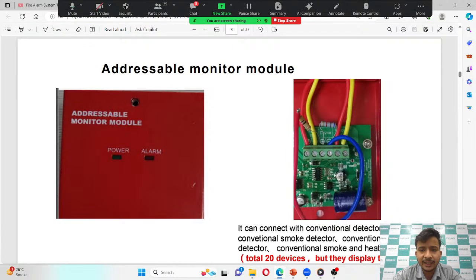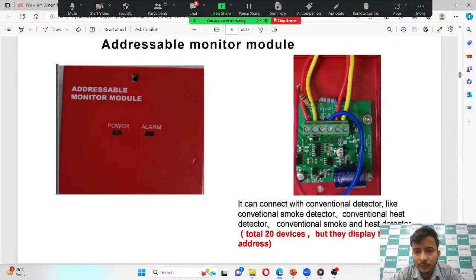Then this is the wiring scheme for the addressable monitor module. As you can see, we have 3 Phoenix connector ports. One is for loop in, as it will be added in a loop, and another one is for loop out. The third one is for adding the device, whatever you are adding, either a conventional smoke detector or heat detector. So one port is for adding that device, and this port has one resistor also. This resistor is mandatory for the communication. If this resistor is removed, it gives an alarm.